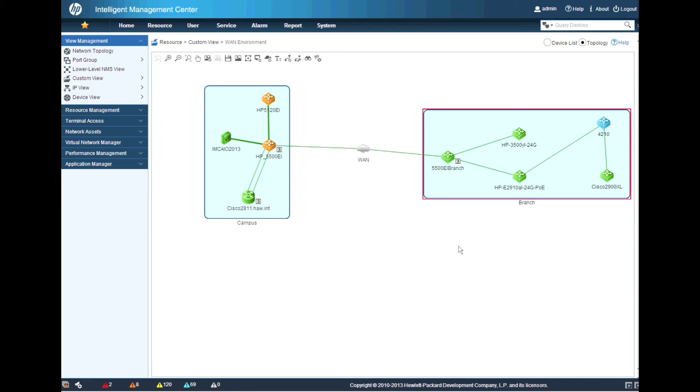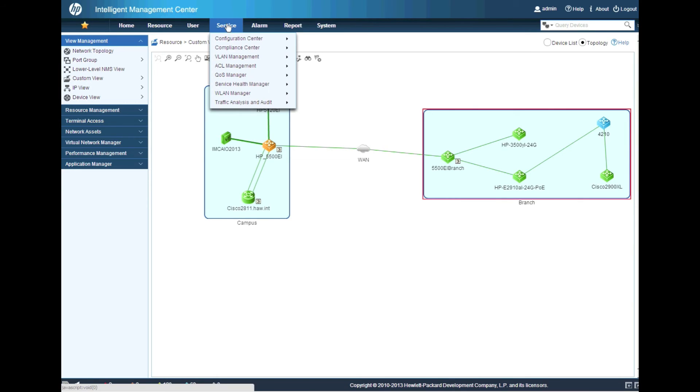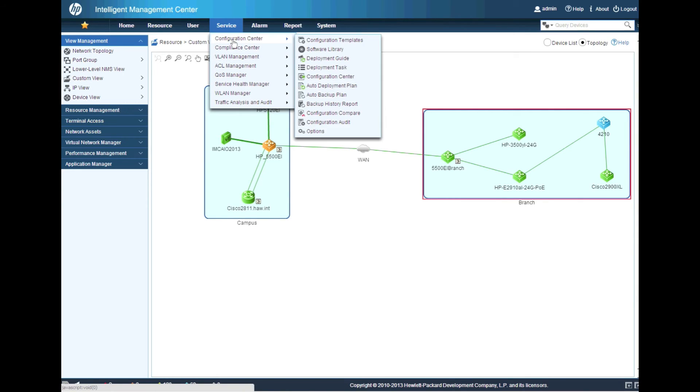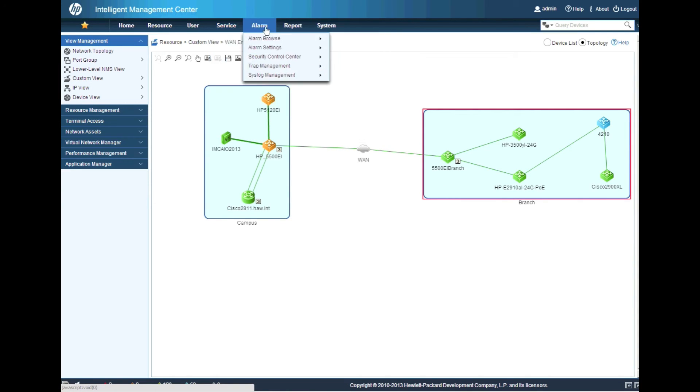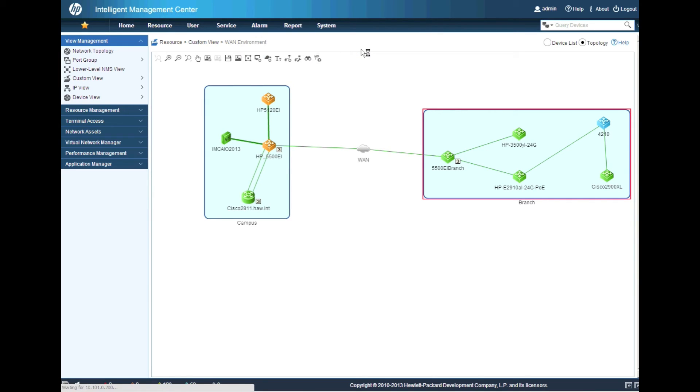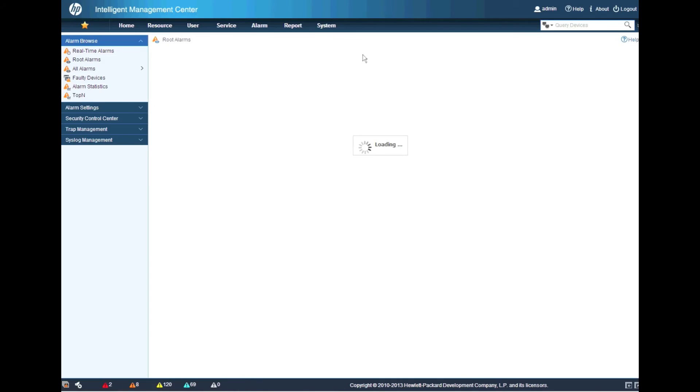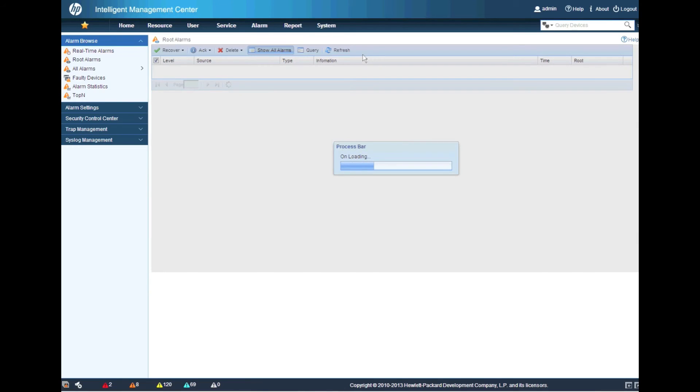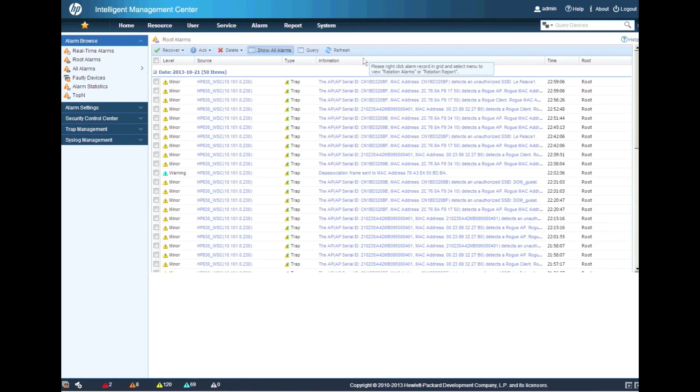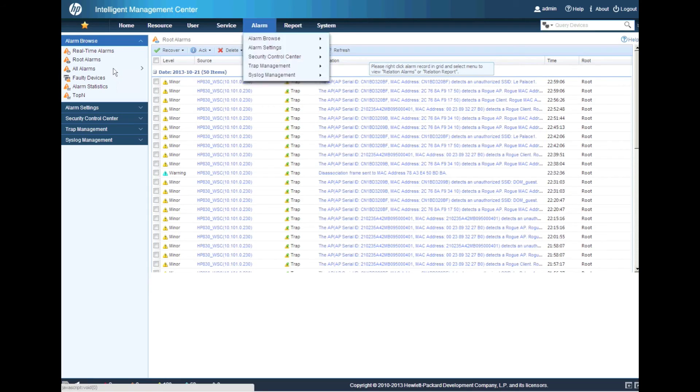So what you've actually seen happen here is as IMC has identified these devices coming back alive, it's automatically going through and recovering from those alarms. So this is no longer a fault state. It's automatically gone through and recovered the alarms and cleared the alarm state.